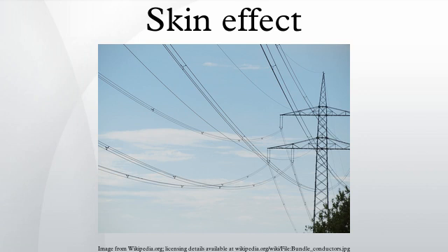The skin effect is due to opposing eddy currents induced by the changing magnetic field resulting from the alternating current. At 60 Hz in copper, the skin depth is about 8.5 mm. At high frequencies the skin depth becomes much smaller. Increased AC resistance due to the skin effect can be mitigated by using specially woven litz wire. Because the interior of a large conductor carries so little of the current, tubular conductors such as pipe can be used to save weight and cost.